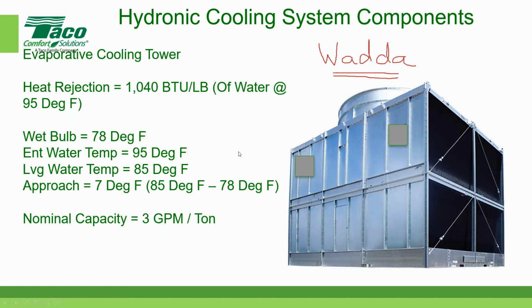So the nominal capacity of cooling towers today is approximately 3 gallons per minute per ton, because it's not only taking the heat rejected by the building, but also the inefficiency of the chiller's compressor. And that's why you wind up with 3 GPM per ton. Remember, we said if you had a 10 degree delta T, that would be 2.4 GPM per ton. Well, in this case, we do have a 10 degree delta T, but 2.4 would not be enough to offset the heat rejection by the chiller itself, or the inefficiency of the chiller. So that's why you have to have more flow for those two things.